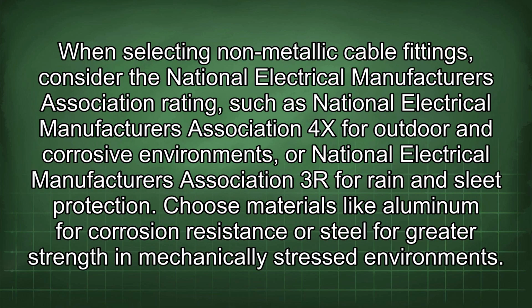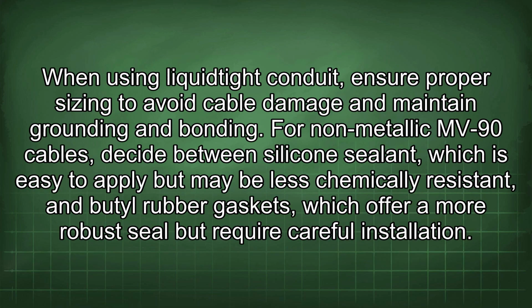When selecting non-metallic cable fittings, consider the National Electrical Manufacturers Association ratings such as National Electrical Manufacturers Association 4X for outdoor and corrosive environments, or National Electrical Manufacturers Association 3R for rain and sleet protection. Choose materials like aluminum for corrosion resistance or steel for greater strength in mechanically stressed environments. When using liquidtight conduit, ensure proper sizing to avoid cable damage and maintain grounding and bonding. For non-metallic MV-90 cables, decide between silicone sealant, which is easy to apply but may be less chemically resistant, and butyl rubber gaskets, which offer a more robust seal but require careful installation.